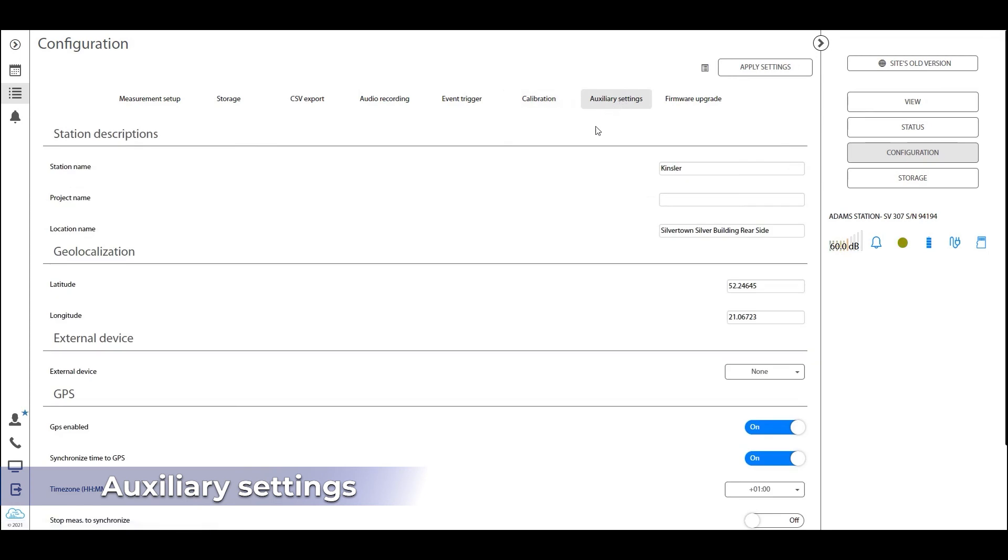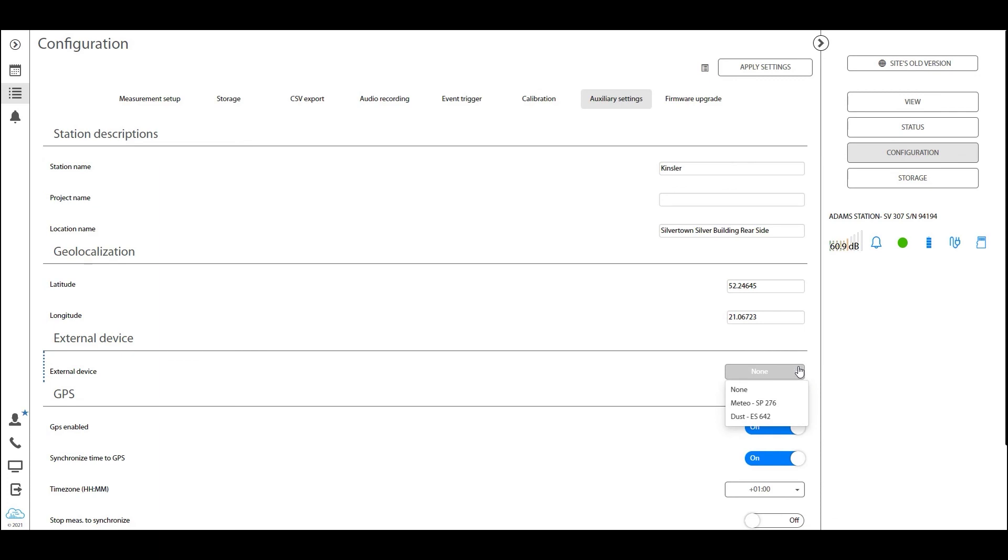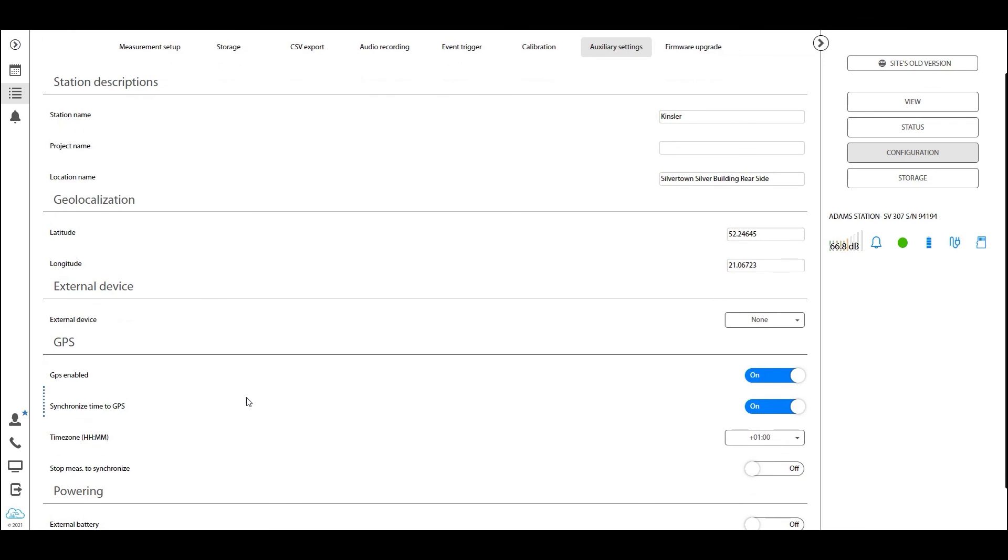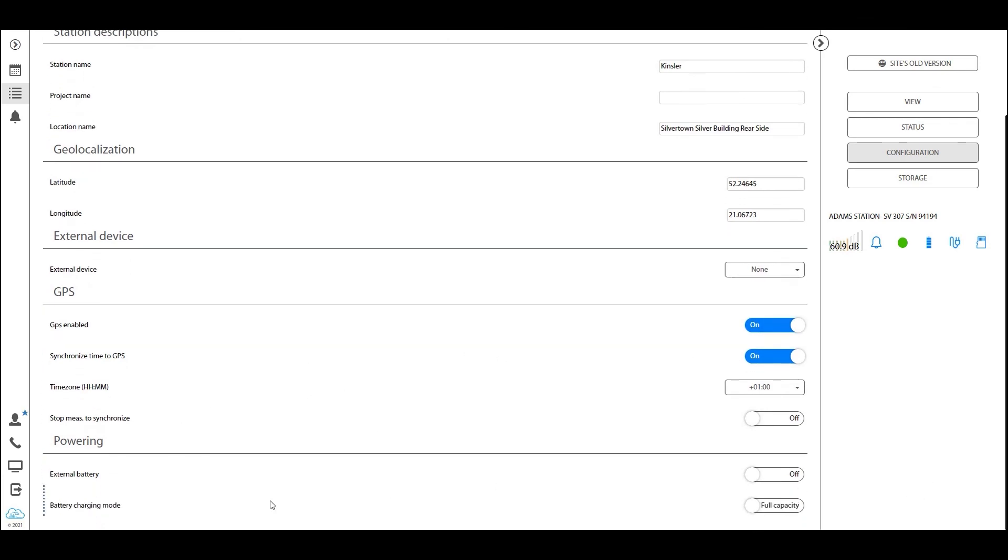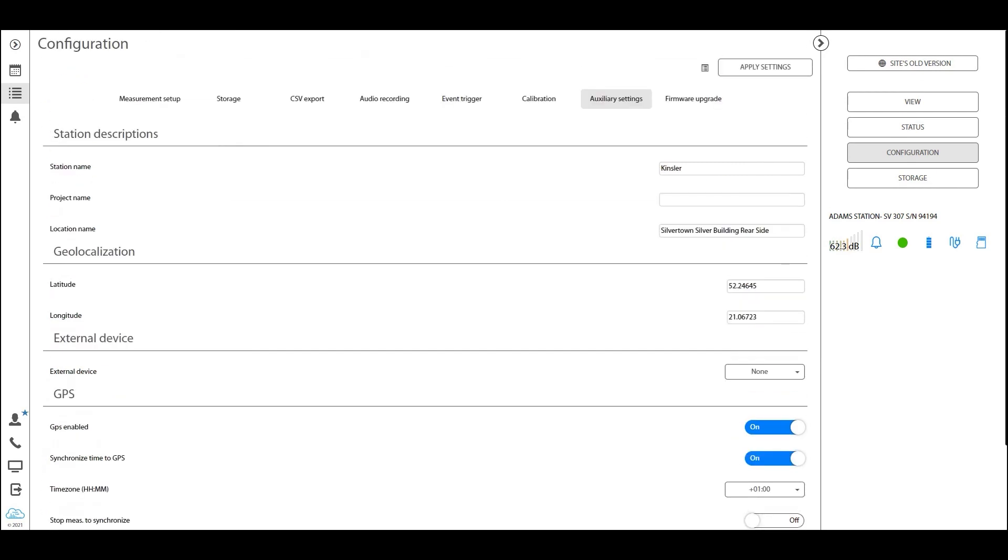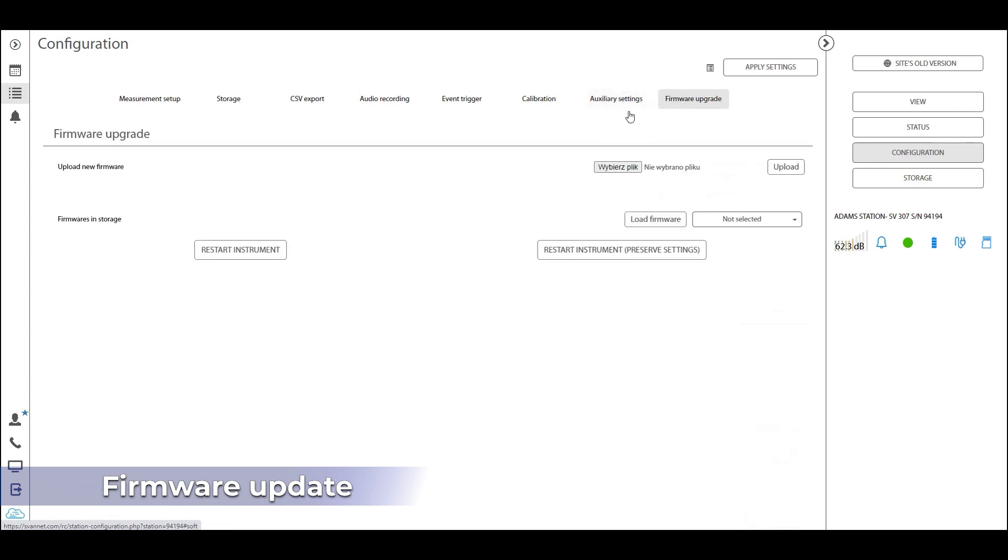As well as the auxiliary settings bar here. The most crucial part is the ability to activate the external device, so whether you have a weather station or dust module connected to your 307, you should go here and activate that so that the station knows that it's speaking to a weather module or dust station. Or activate the GPS, enable the GPS synchronization, and the different charging modes. So you can have the optimized battery charging mode here, making sure that the battery is never charged to 100% when it's in mains and saving the battery's life expectancy and raising it up.